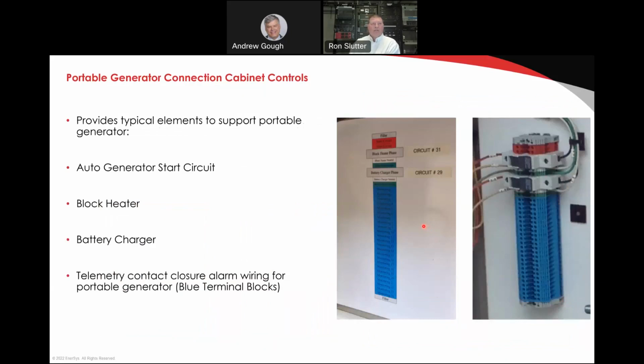You see here we have identified the automatic generator start signal, the block heater, the battery charger, and the telemetry contacts, although they're not connected, are there for connecting telemetry for a portable generation. It's very convenient if you have a long-term downtime for a fixed generator, you're doing a replacement, whatever the case may be, you can still facilitate the installation of a portable generator and know that it's going to give you all of the alarms and start and different capabilities that are really required for that long-term portable generator.